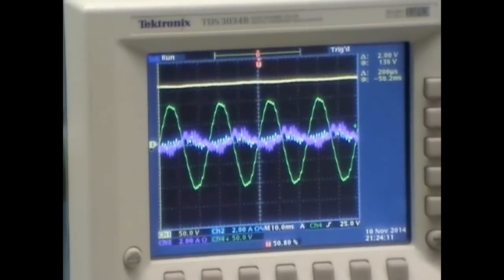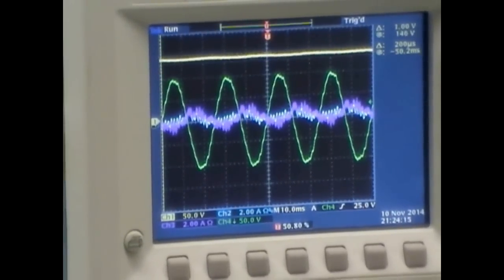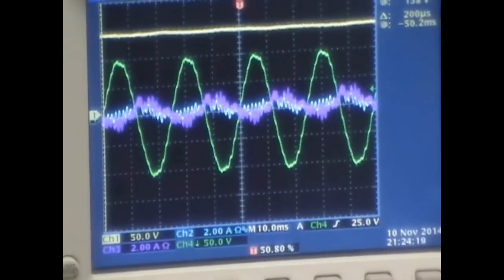So let's observe the transition on these LEDs as we do an AC to DC transition when we ramp down the speed. It went to DC mode and the loading also got reduced. As you can see here again, the waveforms are DC in the stator, the green current. Let's look at the front-end converter waveform as we are ramping down and ramping up the speed. The yellow waveform here is the DC link voltage, which is maintained at 120 volts. The green is the AC grid voltage, and the violet or the blue are basically the current drawn by the front-end converter.